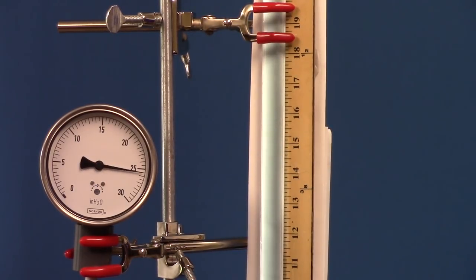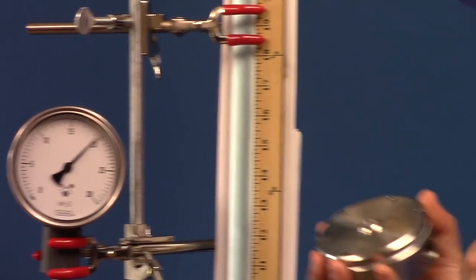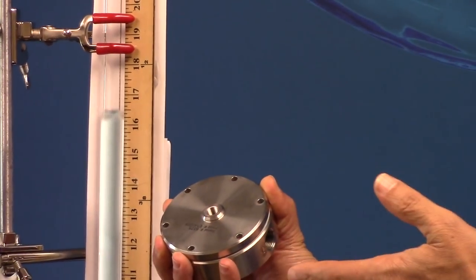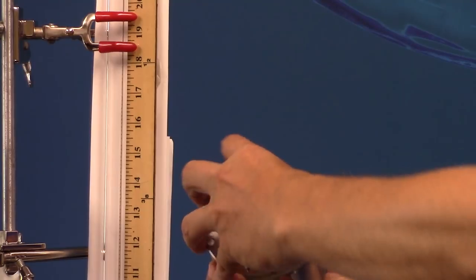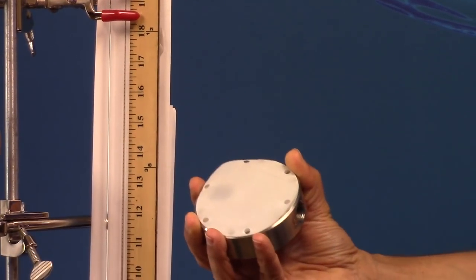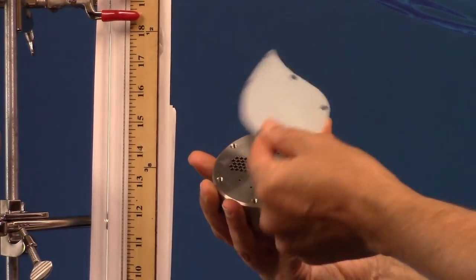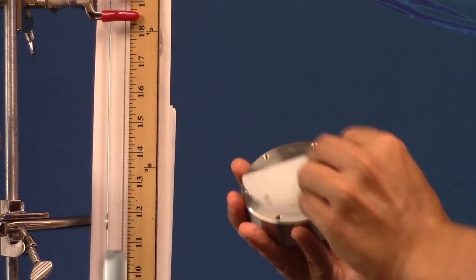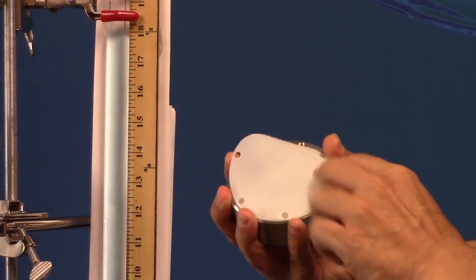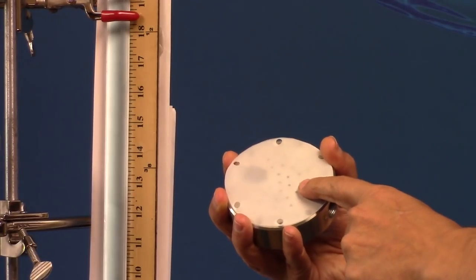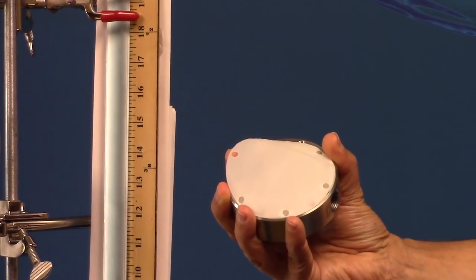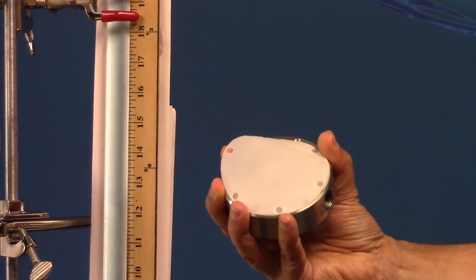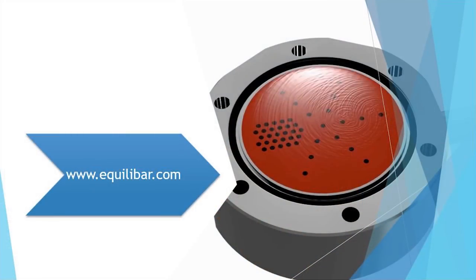The secret of how that Equilibar back pressure regulator works is the fact that there's only one moving part. That moving part is a thin, flexible membrane or diaphragm. Because the membrane is the only moving part and it is so flexible, there's no hysteresis, and it repeats the pilot pressure very precisely in a one-to-one relationship.